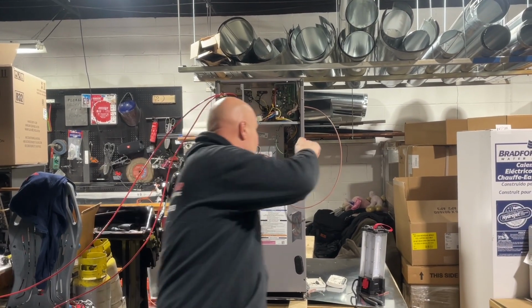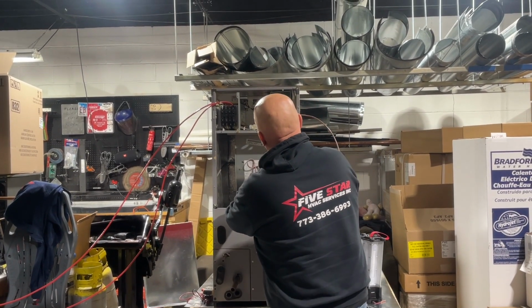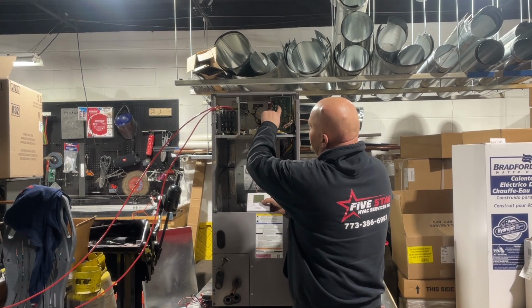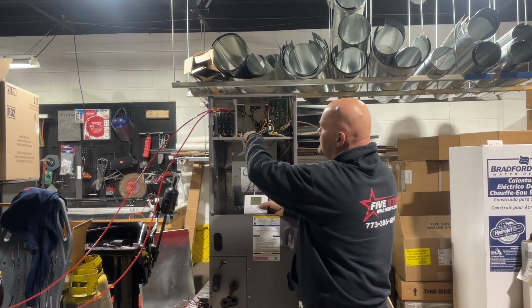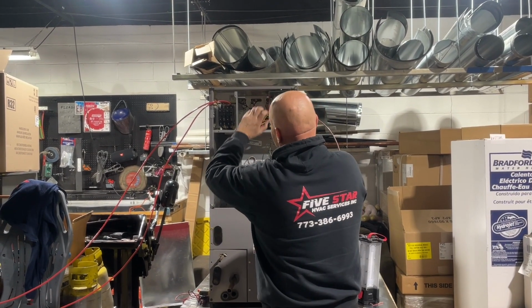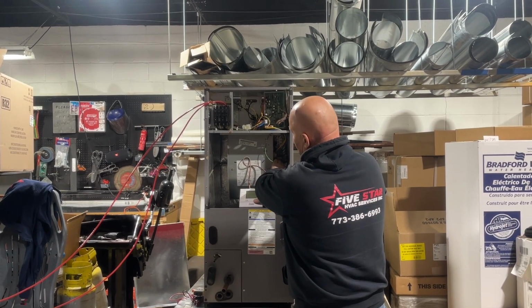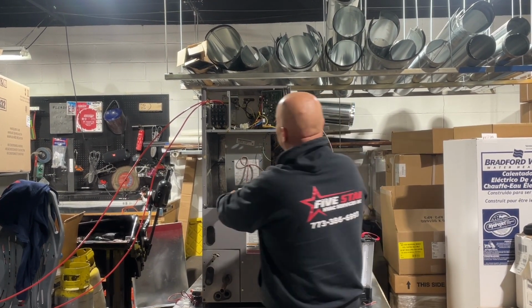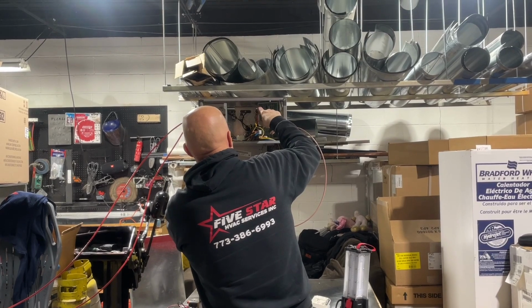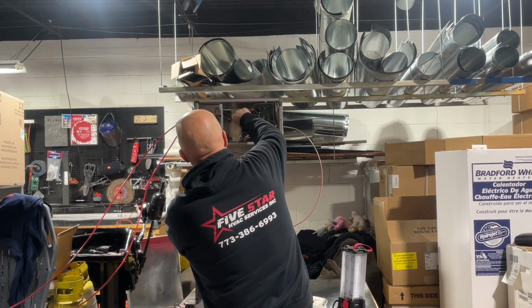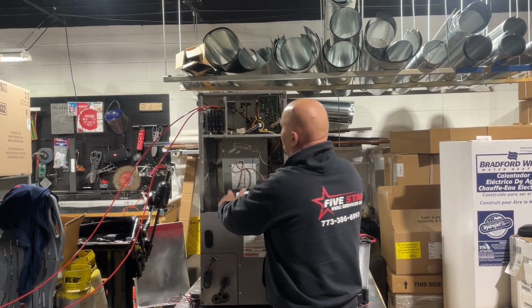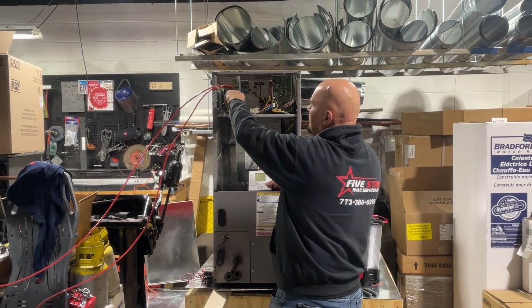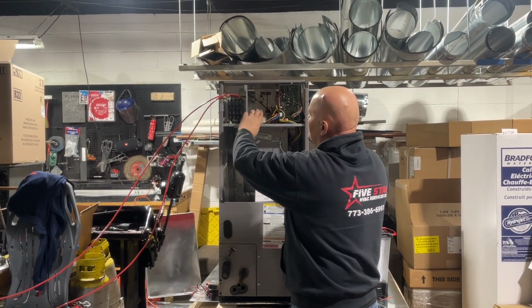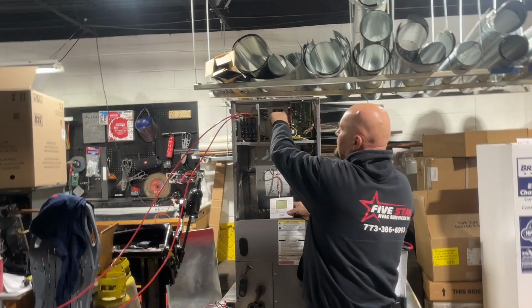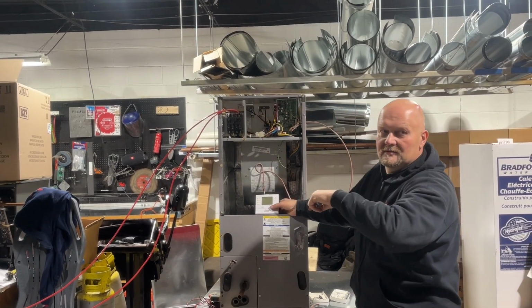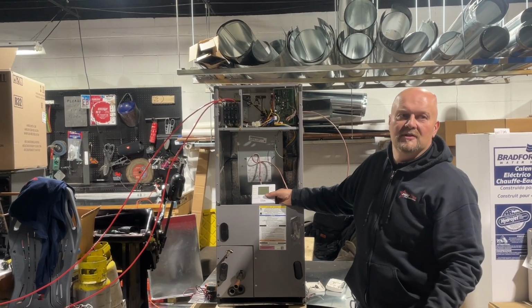Once that happens, the 24 volts in here will engage two separate relays. Whether those relays are inside the control board or actual relays, the same thing will happen. You're going to send 240 volts to the blower motor to engage it, and you're going to send a 24 volt signal to close the sequencer or the relay that's going to take one of these legs and complete the 240 volt circuit into the electric heating section. And that's pretty much the end of the sequence.